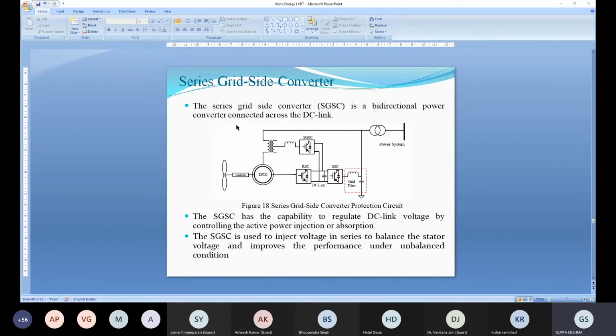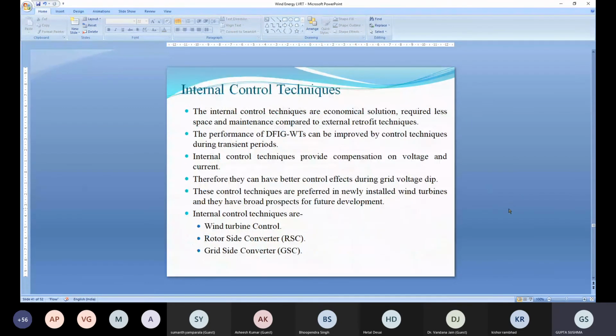So when the grid is unbalanced, it will take the power from the DC link and feed it to the grid and maintain a constant voltage over the grid. So it can compensate the voltage, it can take care of the harmonics, but it takes energy from the DC link. So this circuit has many advantages. These are the external retrofit techniques.